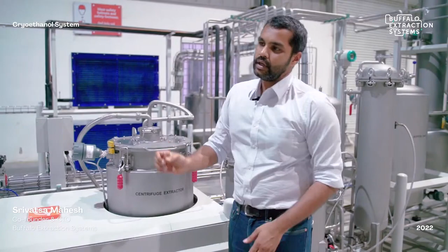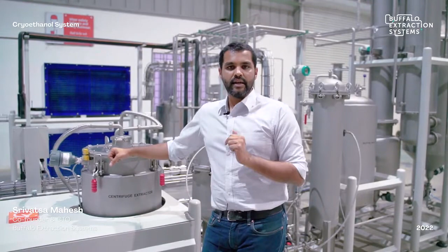and continuing the extraction. The centrifuge basically acts as a typical washing machine, in that you have multiple cycles for washing, where you can rotate the centrifuge in a counterclockwise direction or a clockwise direction. You can set a certain stabilization time or residence time between the cycles, and then you can set a certain spinning time so as to remove all the ethanol from the biomass at a high rotational speed. The maximum rotational speed the system goes up to is about 2000 RPM.